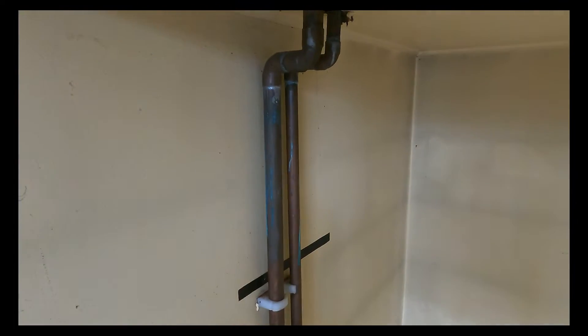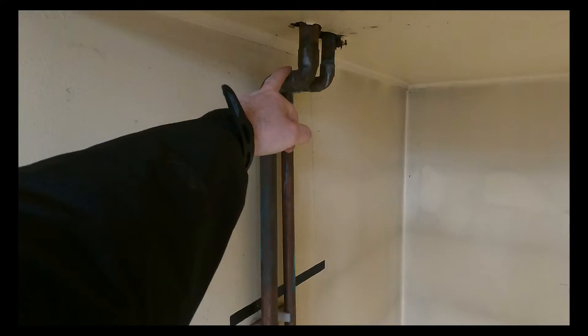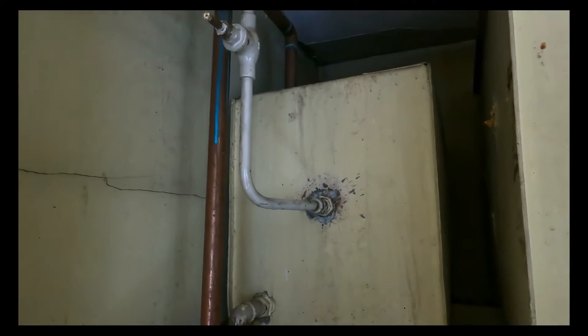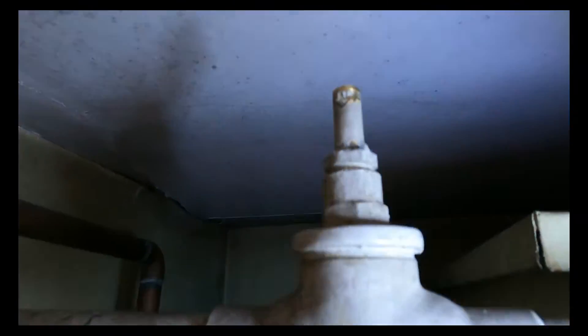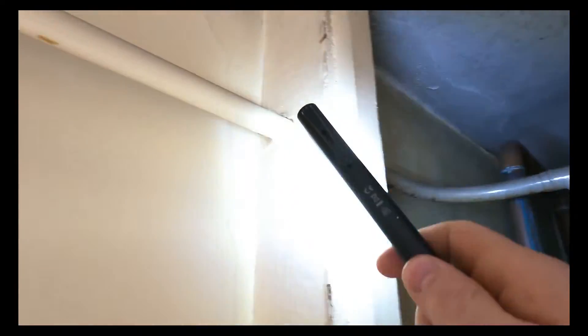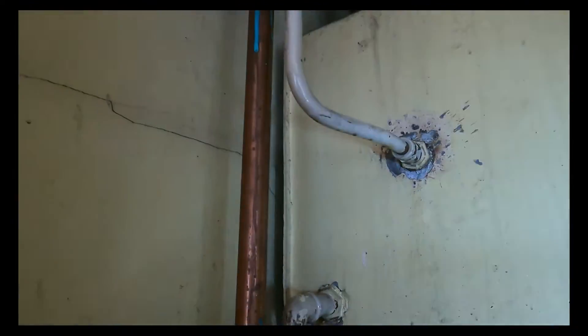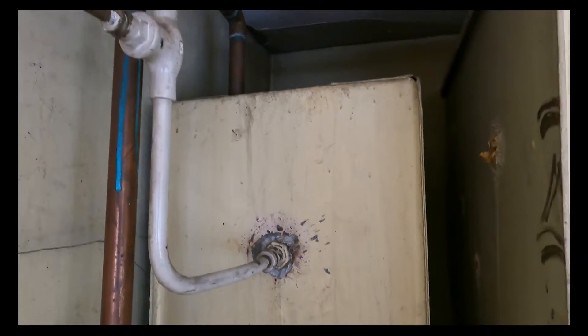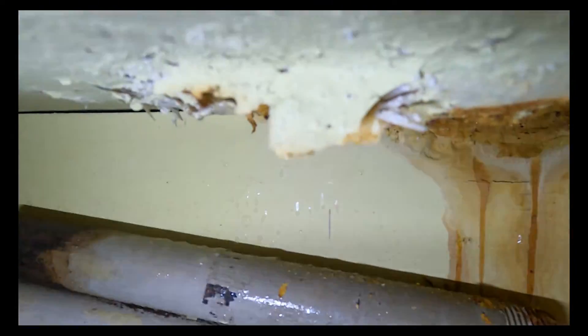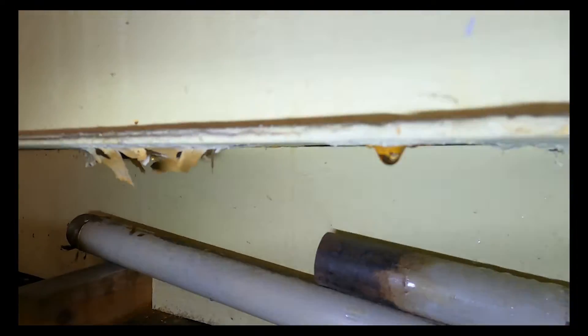It's an open vented heating system - same principles as a domestic property. 28mm expansion, 22mm cold feed. You can see here there is my old - I mean that must have been in from day one by the looks of it. We've even got the three-quarter stop tap - the head's been snapped on that. So we've turned the water off to the building now. Issues as you can see - we've got a leaking tank there. The feed and expansion tank looks well and intact but galvanised over the years they start rotting, and this one here you can see underneath is totally pitted away. You can see just out of these little holes there. Same with that one there - I don't want to start poking it as it's got a bit of water. I'm just going to get this drained off now.